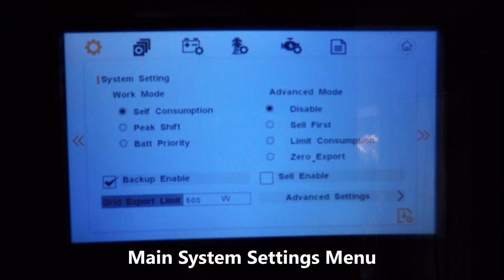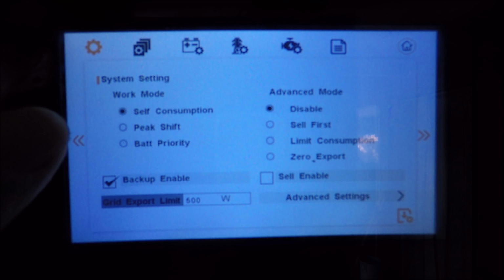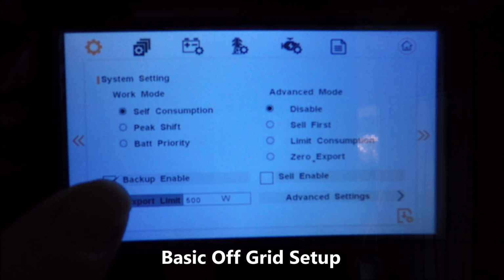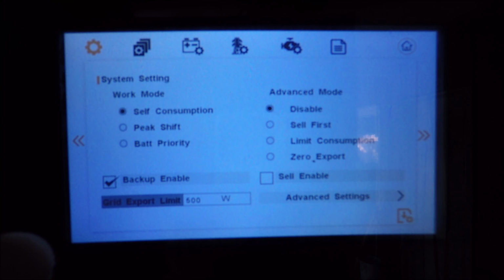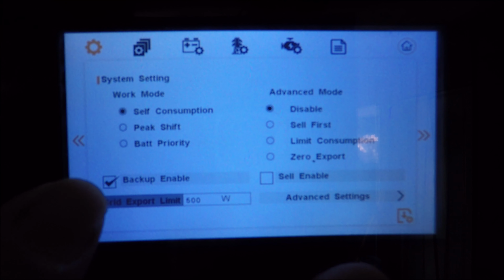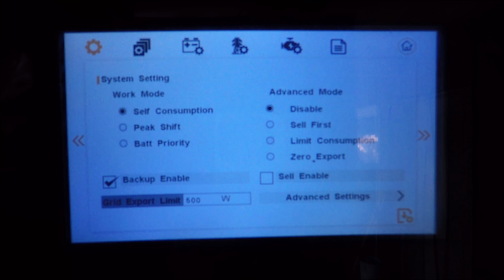For basic off-grid setup, we're going to use self-consumption. We are going to keep backup enabled and keep that box checked. As long as you keep this checked, in the event that the grid and the PV are unavailable, the battery will supply power to all of the loads. Think of this as kind of a UPS mode for the inverter. It's a best practice to keep this on so that you have an uninterruptible power source to your home. If you disconnect this and the grid and the solar go out, then you will lose power to your loads.